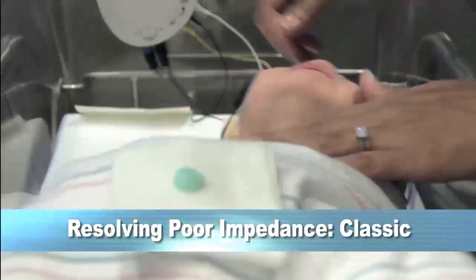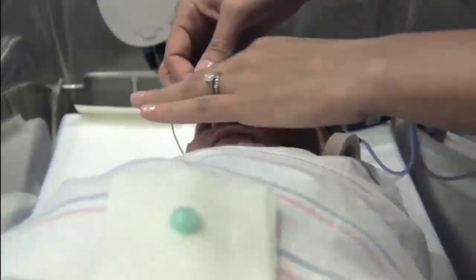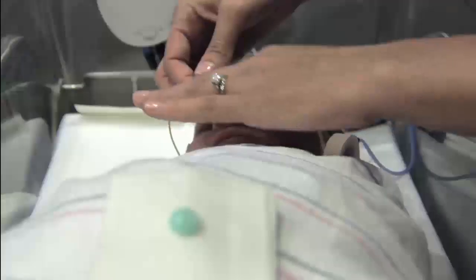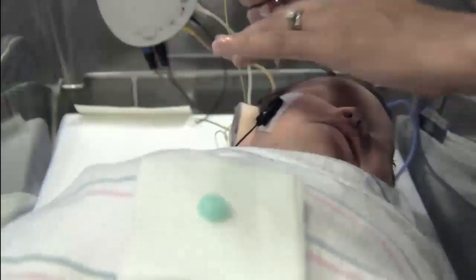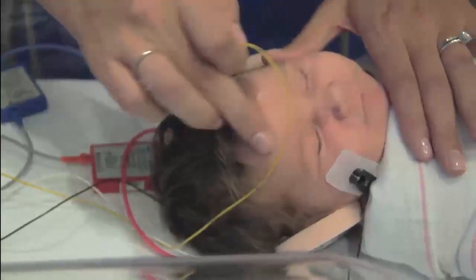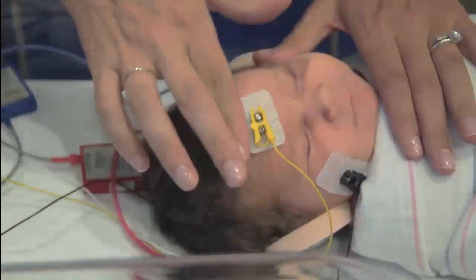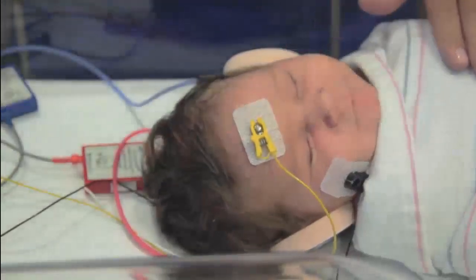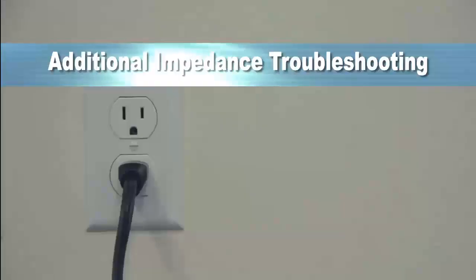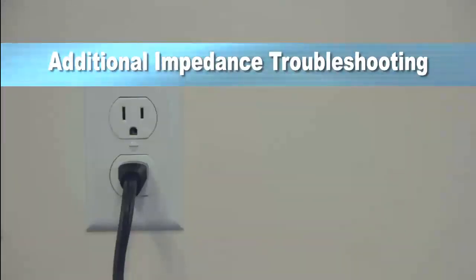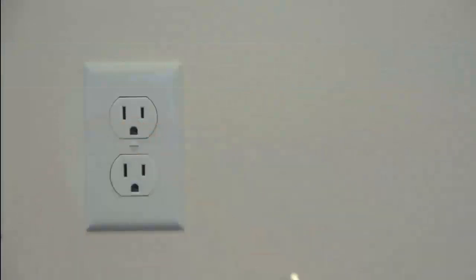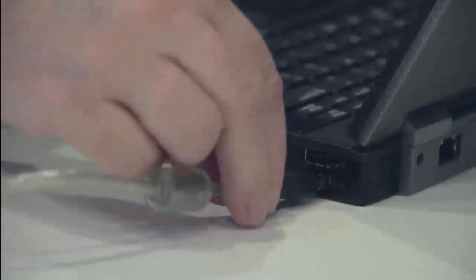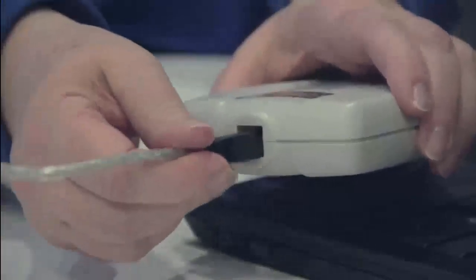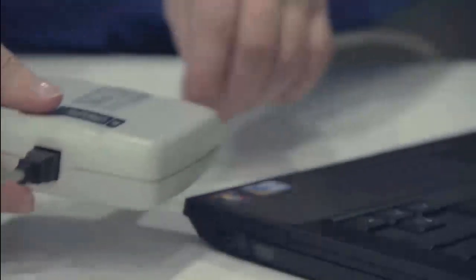Check that the disposable electrodes are securely adhering to the baby's skin at the prepared locations and that the electrode wires are securely attached. Lift off the electrode that shows poor impedance and rub a little more new prep into the skin. Wipe off the new prep and reapply the electrode. Depending on skin type, you may need to apply a new electrode if the original electrode will not adhere securely to the skin. If you continue to experience a problem achieving good electrode impedance, try testing on PC battery only rather than using AC electricity. Also check the connection of the MB11 USB cable to the PC and to the MB11 hardware module to make sure that it's securely connected on both ends.